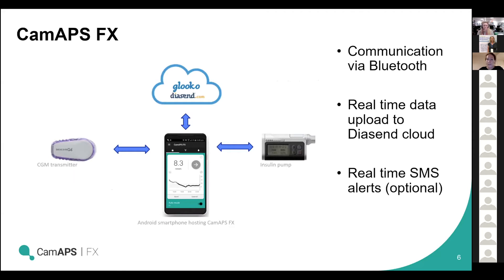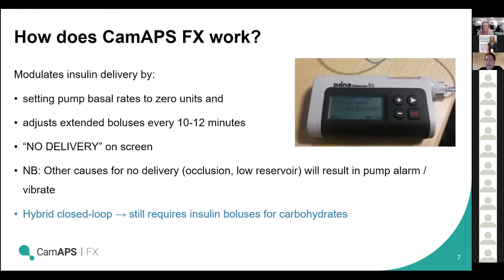Just by way of a reminder — many of you will be familiar with this — this is the CAM APS FX system: the Android smartphone which hosts the app, which acts as a CGM or glucose sensor receiver and communicates with the Dana RS, Dana R, or soon to be Dana I pump, and the data is automatically uploaded to the Diasend cloud. The system works by modulating insulin delivery, pushing the pump basal rates down to zero units and then allowing it to adjust an extended bolus every 10 to 12 minutes. This is really important in terms of understanding why certain settings make a difference with this system and why others don't.